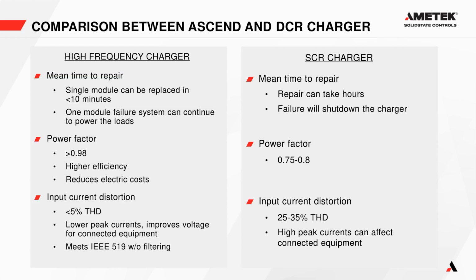It also has lower peak currents that will not affect connected equipment as much as the DCR would. And we also meet IEEE 519 without filtering on the Ascend charger. The internal modules provide load sharing and have built-in redundancy, whereas with our older DCR, SCR-based charger, there is no redundancy within the system. It would require multiple systems for redundancy.